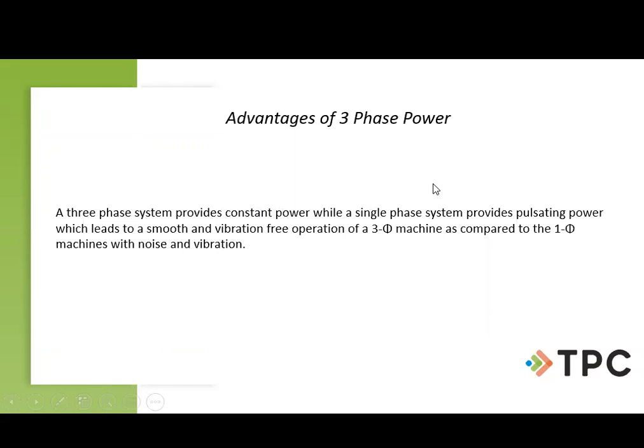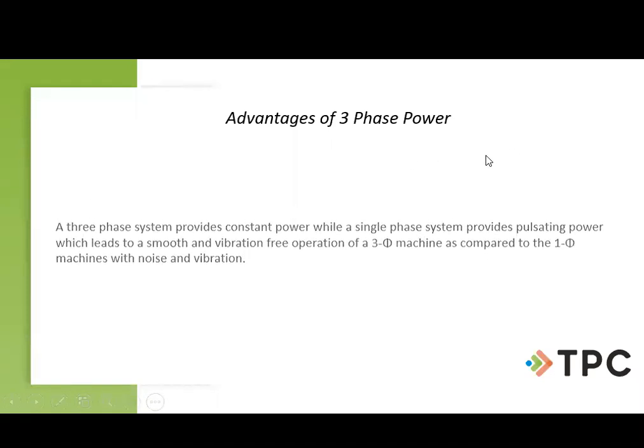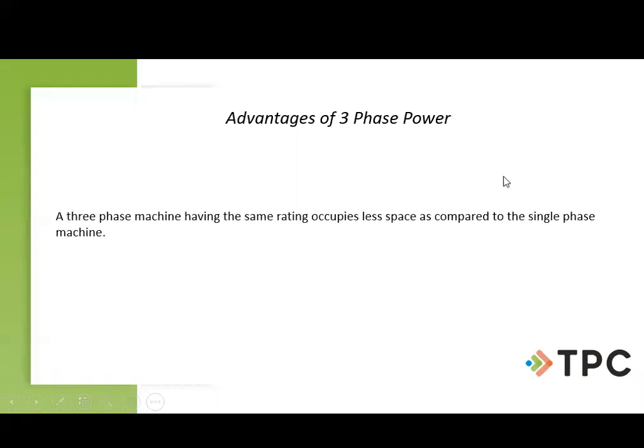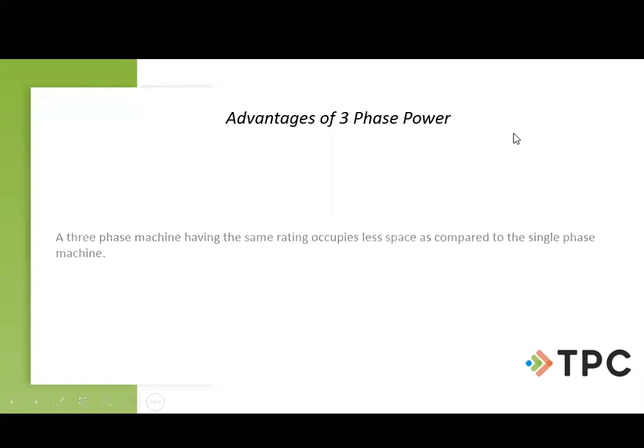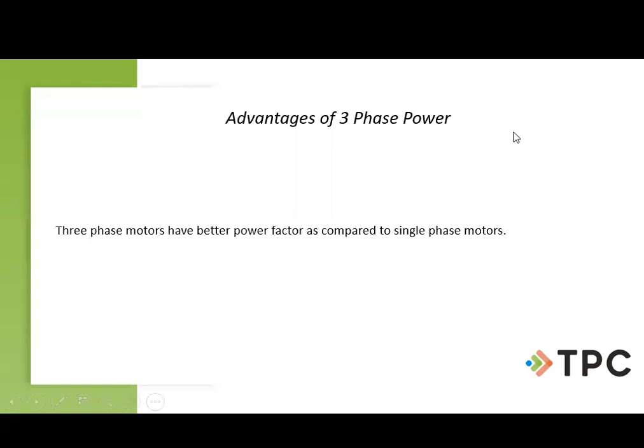And we're not going to have any type of pulsating power like we might with single phase with just the one sine wave. And so with the three sine waves, our equipment is just going to run smoother, less noise, less vibration, because we're not hitting zero at all with three phase. One of our windings will always be up near the peak, and it's going to occupy less space. So if we talk to management, right, space is money, and no question about it. If I can put more machines in the same square footage area and make more product, I'm going to be more profitable. So three phase would definitely allow us to make that. The three phase motors are going to have a better power factor than single phase, and so we're not going to waste as much electricity in that case.